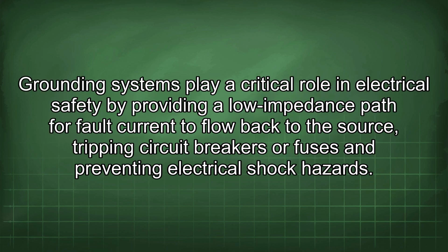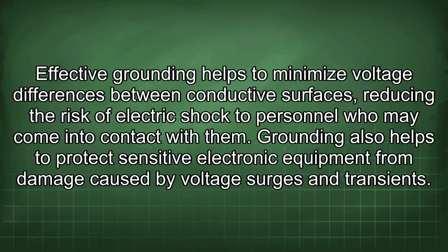Grounding systems play a critical role in electrical safety by providing a low impedance path for fault current to flow back to the source, tripping circuit breakers or fuses and preventing electrical shock hazards. Effective grounding helps to minimize voltage differences between conductive surfaces, reducing the risk of electric shock to personnel who may come into contact with them. Grounding also helps to protect sensitive electronic equipment from damage caused by voltage surges and transients.